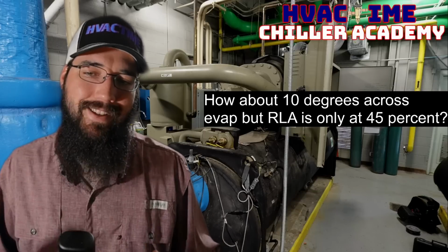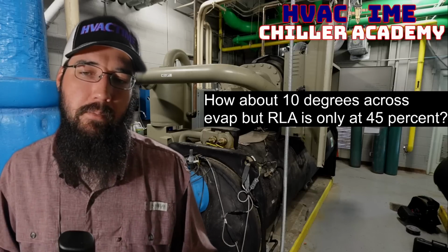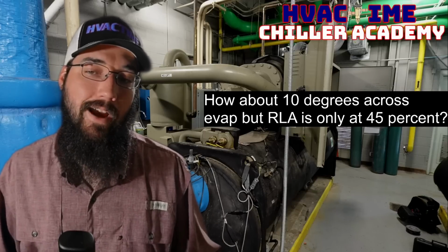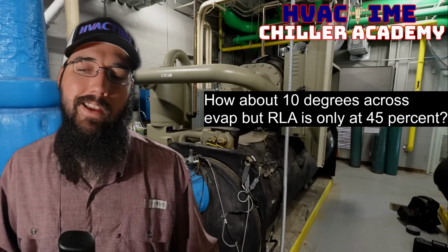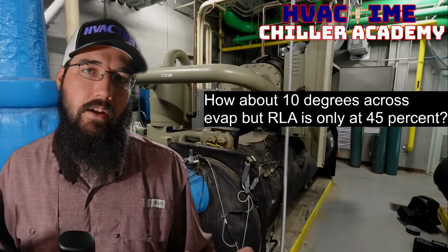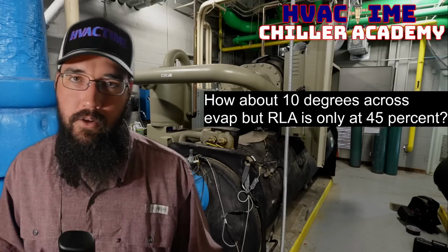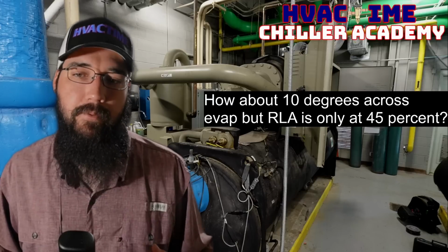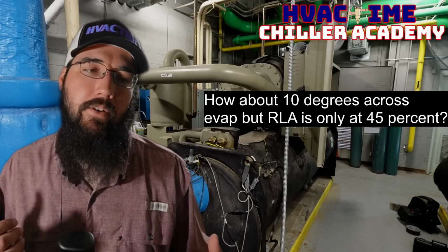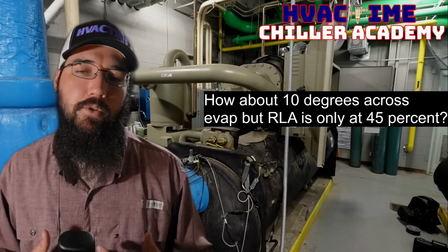How about 10 degrees across the evaporator, but RLA is only at 45%? Now, this is in the context of a machine being loaded or not loaded, or the chiller being loaded or not loaded.